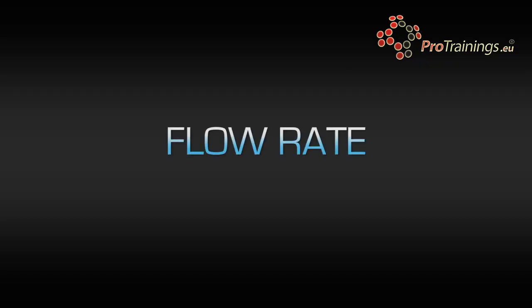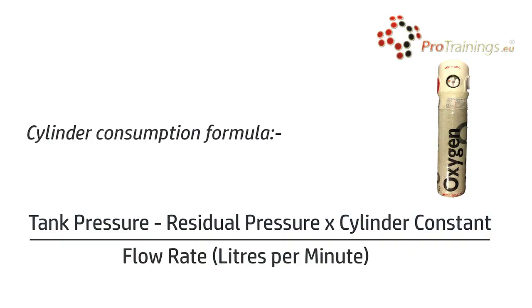In our example we are calculating the time a D size cylinder will last, so we'll use the constant figure of 0.16. The final figure we need is the flow rate in litres per minute. The usual maximum flow rate for regulators is 15 litres a minute. This may be higher in specialist applications like scuba diving, where the flow rate could be 25 litres per minute. In our example we'll use the usual maximum of 15 litres a minute.